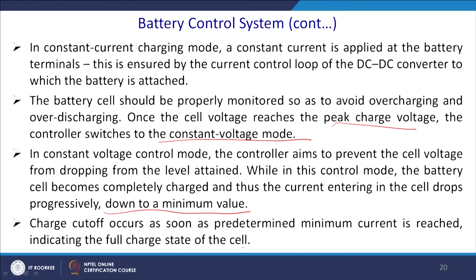In the constant voltage control mode, the control aims to prevent the cell's voltage from dropping from the level at which it is maintained. While in this control mode, the battery cell becomes completely charged and thus the current entering the cell drops progressively from the maximum value. Then a charge cutoff occurs as soon as the predetermined minimum current is reached, indicating that the battery is fully charged. So, this is the way your battery management system will work.